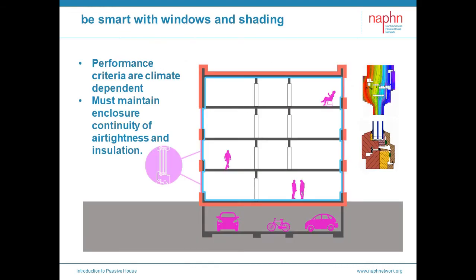We will utilize passive solar heat gains, as windows can be designed to be a substantial part of our heating systems, but we do so while being very conscious about the energy balance, providing solar protection and considering the consequences. Restraint might be a good word. A key concept is that windows and doors act not simply as a provider of views, daylight, and passive heat gains, but as a critical component in our continuous insulation and airtightness layers. The windows themselves are often triple pane, truly thermally broken, and airtight with three layers of gasketing. The window connections to surrounding airtight and insulation control layers must be airtight and insulated — thermal bridge-free connections. This gets you deep into the construction details and the power of those details.